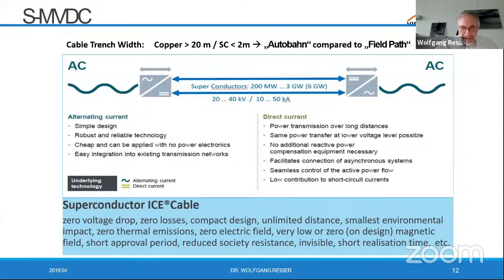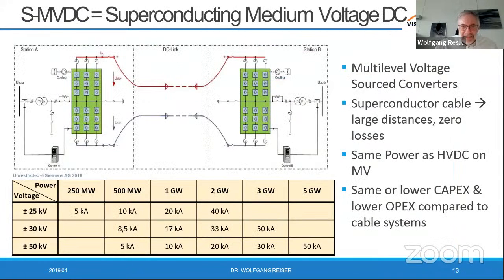Go to the next page, and that is the more important one. If you see here the multilevel voltage source converters, you can easily imagine that with a level of plus minus 50 kV, we can reach 50 kiloamps, 5 gigawatts. That is the range we are looking for, even going up to 10 gigawatts, with the same or lower capex and definitely lower opex compared to cable systems.